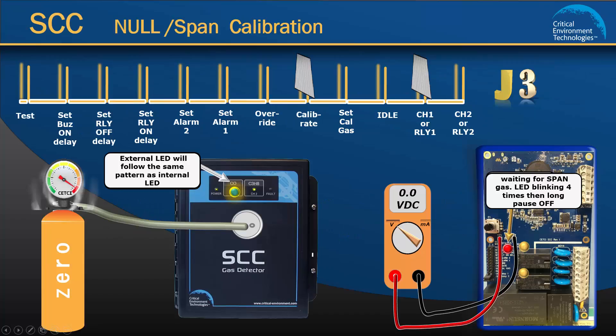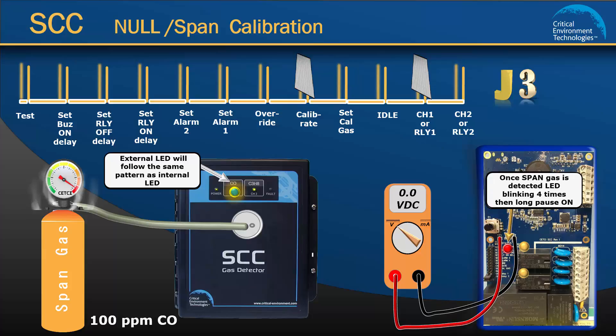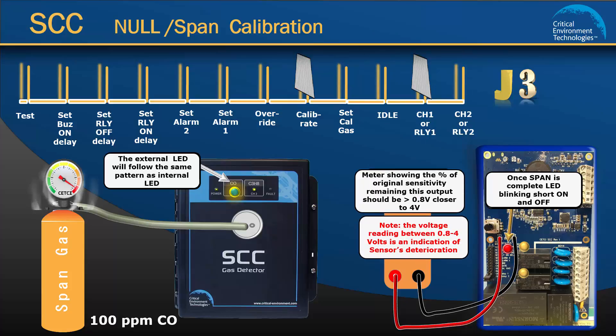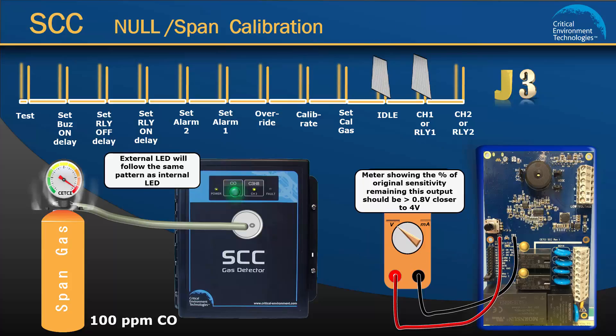To continue with span calibration, attach the span gas cylinder and open the regulator valve fully to allow the span gas to flow over the sensor. When the gas flow is detected, the internal and external LED lights will blink 4 times and then long pause on. Once the gas is detected, spanning will take 2 to 3 minutes. The voltmeter reading will start increasing. When the spanning has completed successfully, the internal LED and external channel 1 LED lights will blink short on and off. The voltmeter will show the percentage of the original sensitivity remaining of the sensor. The reading should be greater than 0.8 volts. The closer it is to 4 volts, the more life there is remaining in the sensor. Remove the jumper from the calibrate position and return it to the idle position. This completes a successful calibration of channel 1.